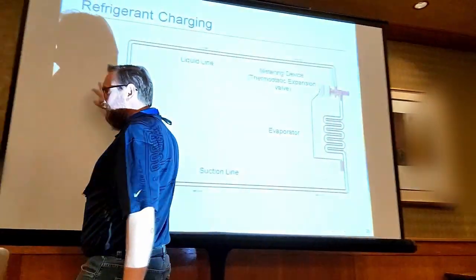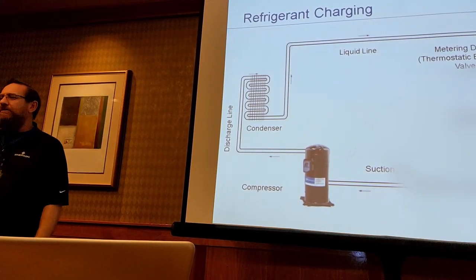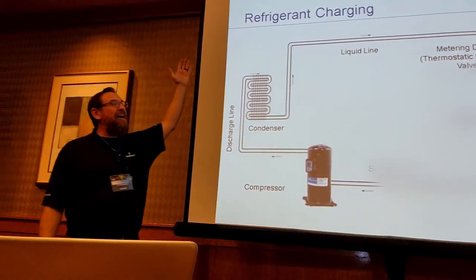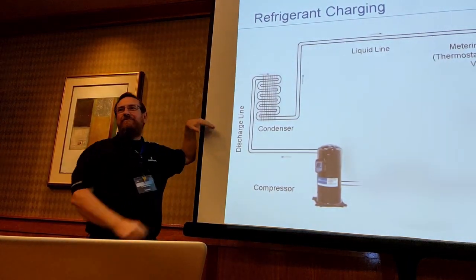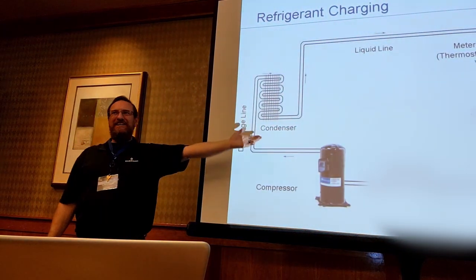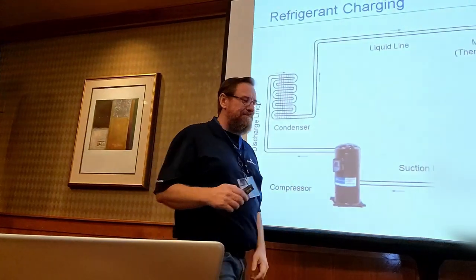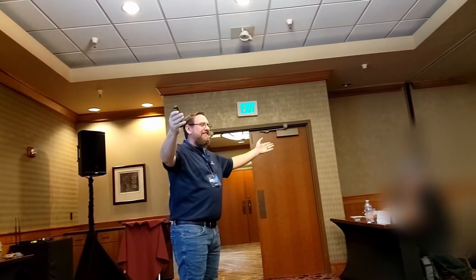What about the condenser? The saturated temperature needs to be higher than the outdoor air temperature. Old units used to have a 30–35 degree difference. Now some high-efficiency equipment is only a 10 degree difference. So what was high pressure then may not be high pressure now — and we have 250-something different types of refrigerant. Saturated temperature is something I can work with and compare. Please don't call me with just pressures — I want saturated temperatures.